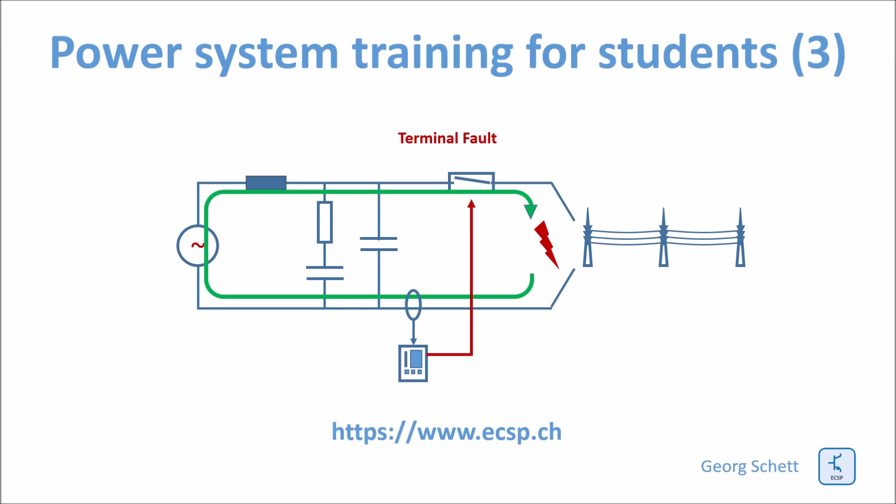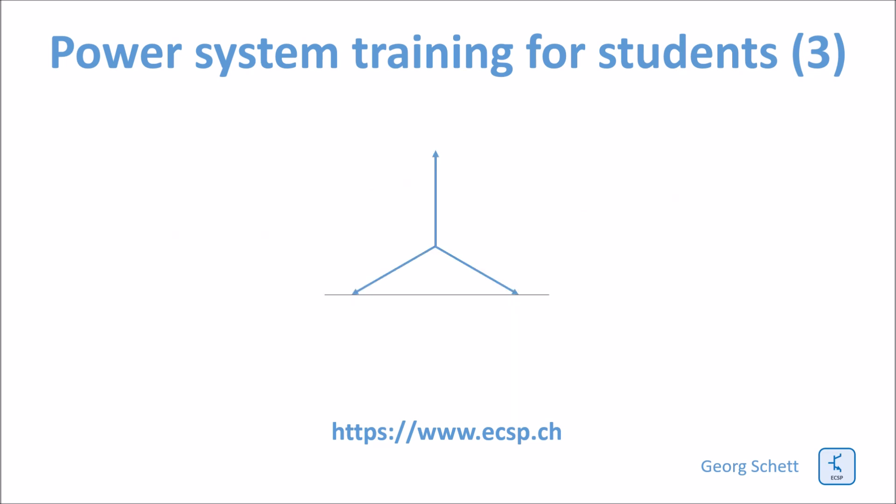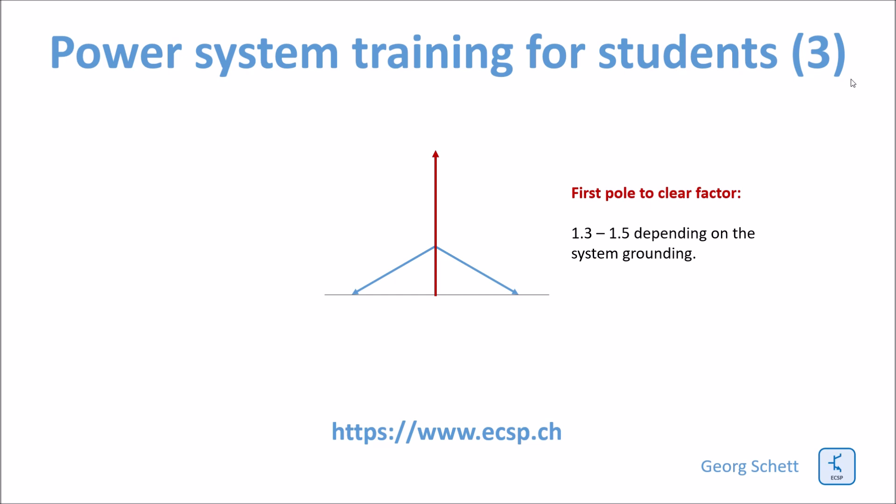In reality, we do not have such a simple single phase network. We have a three phase system. And in a three phase system, there is another issue. You have the so-called first pole to clear factor. Here you see the voltages of the three phases. The first pole clear factor is normally 1.3 to 1.5. So that means that the TRV of the first pole to clear is 1.3 to 1.5 times higher than just the single phase TRV we have simulated before.